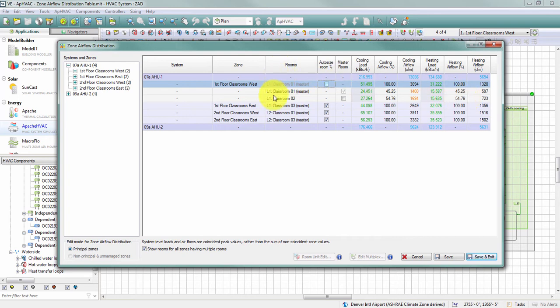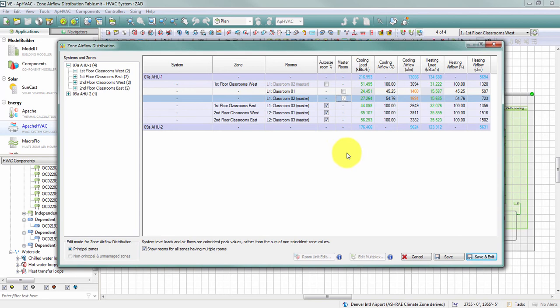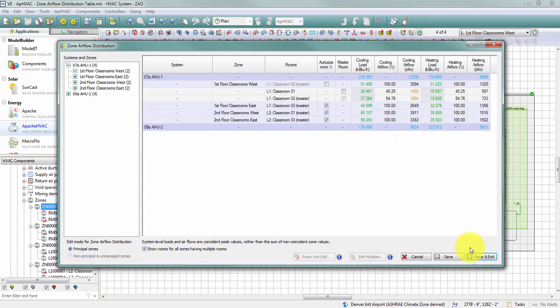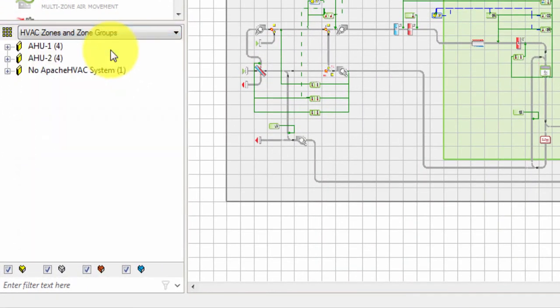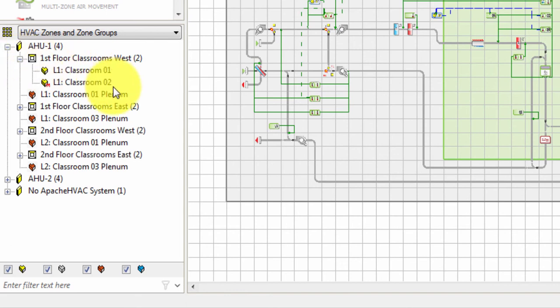When the zone is expanded to show its spaces, the table also indicates which space is the master space — the one containing the thermostat that controls zone behavior. In my example, classroom 1 is the master. I can change this using the master room checkbox without leaving the table. Checking classroom 2 makes it the master, and after saving the table, the change is reflected in the HVAC zones and zone groups browser, where classroom 2 now shows the red M symbol.